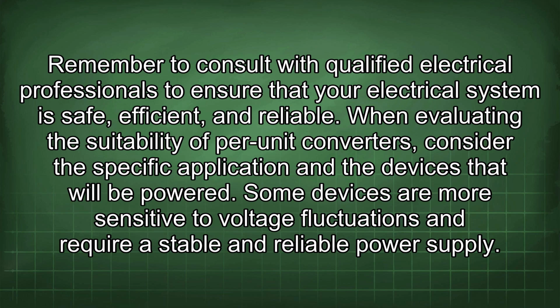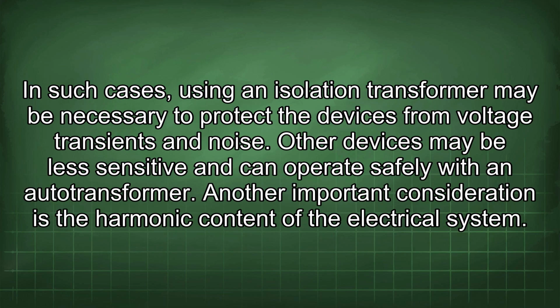When evaluating the suitability of per-unit converters, consider the specific application and the devices that will be powered. Some devices are more sensitive to voltage fluctuations and require a stable and reliable power supply. In such cases, using an isolation transformer may be necessary to protect the devices from voltage transients and noise. Other devices may be less sensitive and can operate safely with an autotransformer.